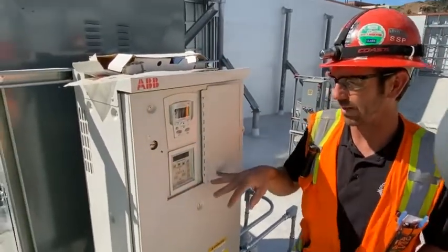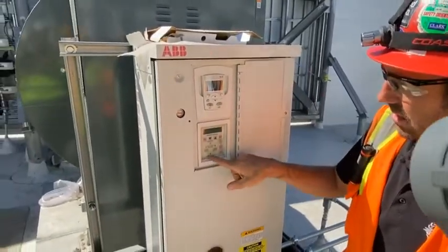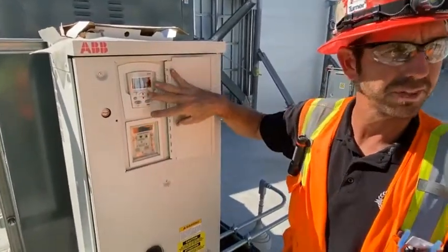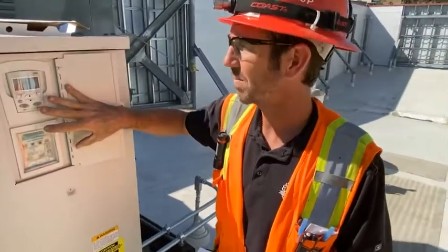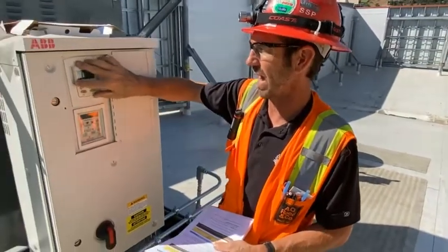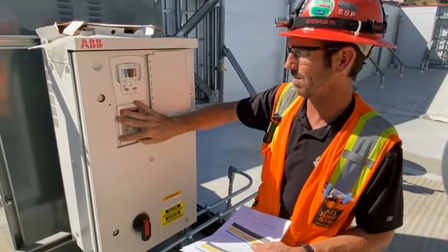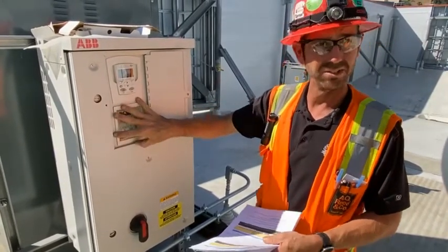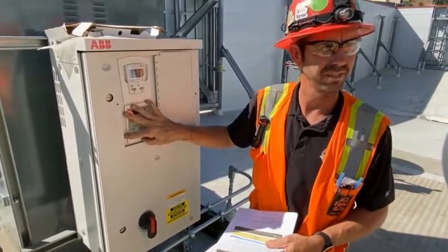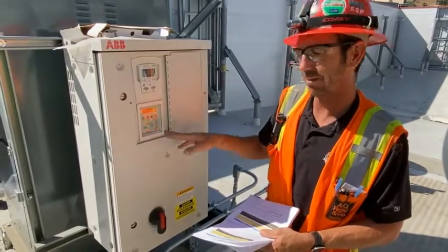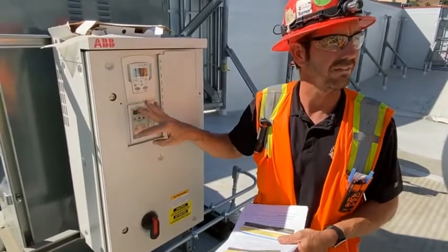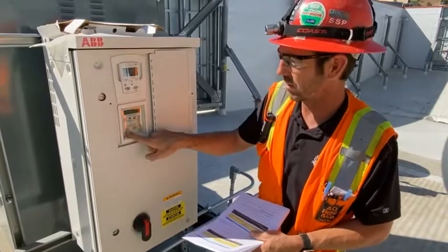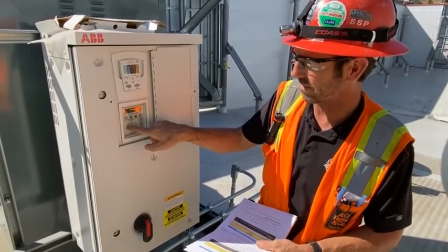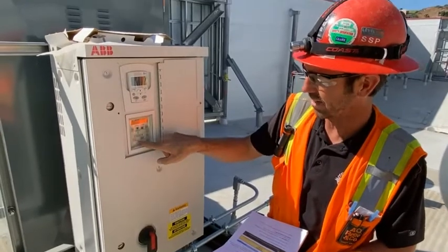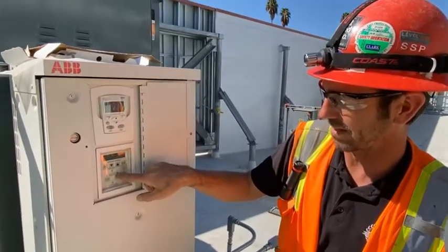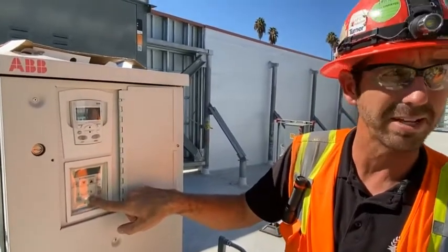The most important part of this unit is the functions down here. Are you guys all familiar with ABB drives at all? So this is the ABB drive keypad, and this is a bypass keypad interface. We are never using the bypass interface up here, okay? It's an extra feature. I tried disabling it, but it always throws an alarm code, so I left it on, but just know that we always want this light over here to be in drive. This is a green light right here. We want to be in drive mode. We don't ever want the light over bypass to be green, okay? We're not ever operating in bypass mode.